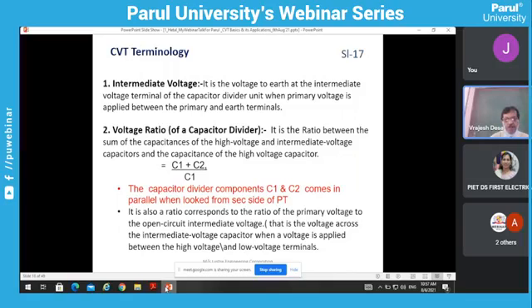So here, on one side we keep 100. The example is one, and on the two sides 20. What happens is the capacitance is inversely proportional, so it comes to around 20. So what we did is connect a 20 kV transformer. We call it the intermediate PT. So primary side and secondary side have different taps, one, two, or three.